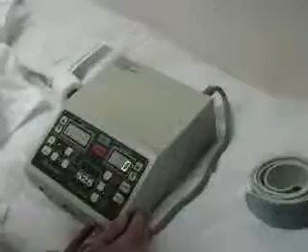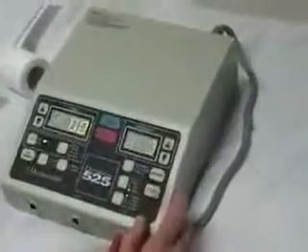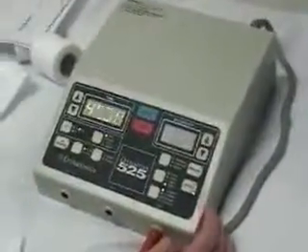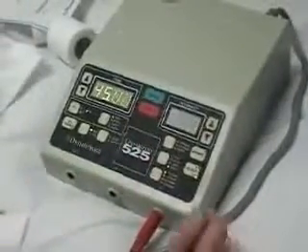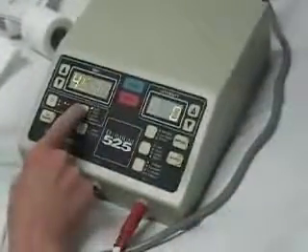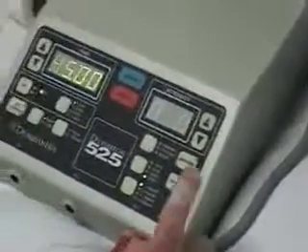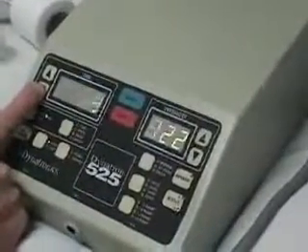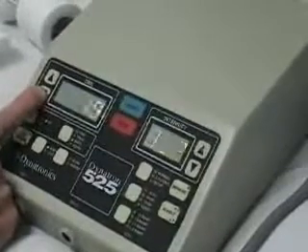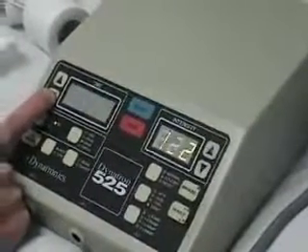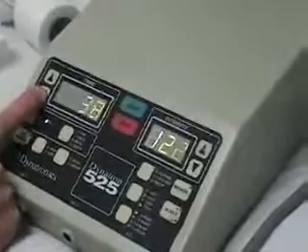And depending on the phase of healing that the wound is in, depends on the setting, and from research they've determined which phases appear to be negative or positive. There's really no 100% agreement because different studies have different ones, but generally they know which is better for which healing. So because she has some necrotic tissue, she's going to be negative. Again, the pulses per second vary depending on what the wound's looking like, so she's going down to 30 pulses per second. The intensity recommended is between 100 and 150.